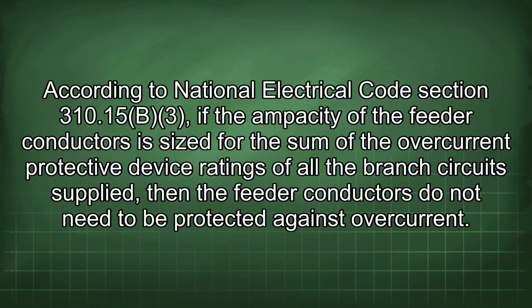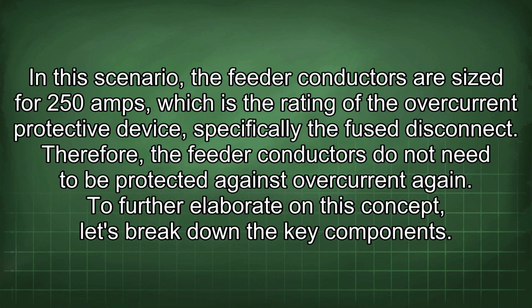According to National Electrical Code Section 310.15(B)(3), if the ampacity of the feeder conductors is sized for the sum of the overcurrent protective device ratings of all the branch circuits supplied, then the feeder conductors do not need to be protected against overcurrent. In this scenario, the feeder conductors are sized for 250 amps, which is the rating of the overcurrent protective device, specifically the fuse disconnect. Therefore, the feeder conductors do not need to be protected against overcurrent again.